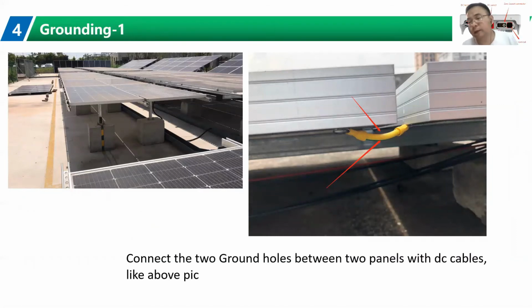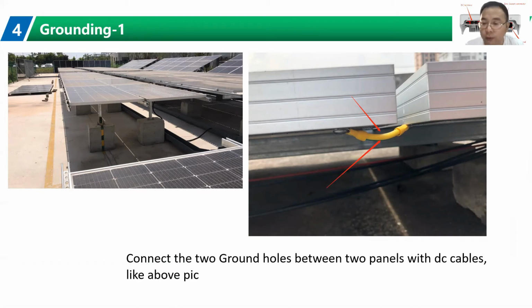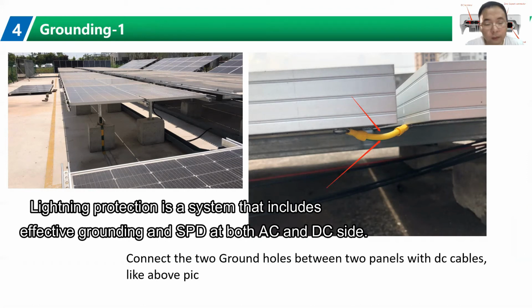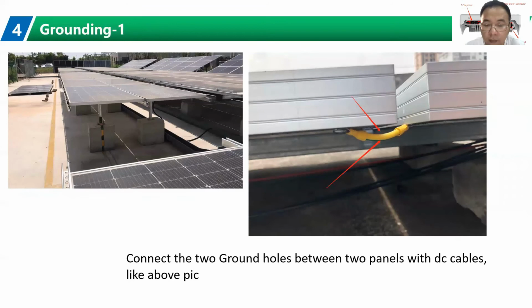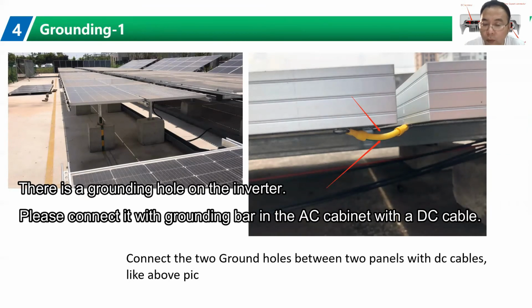Okay, let's discuss the grounding. About 90% of inverters are damaged by lightning, so the grounding is very important. Lightning protection is a system that includes effective grounding and SPD at both AC and DC sides. There is a grounding hole on the inverter.